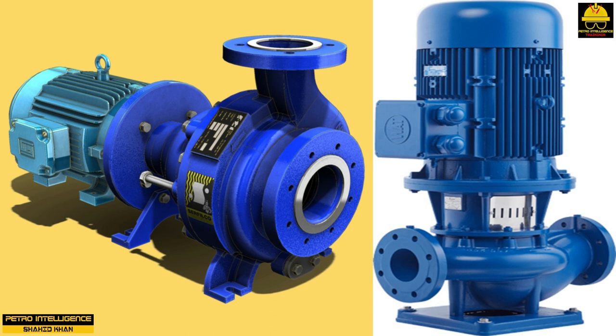Another term used in the operation of a centrifugal pump is net positive suction head required, NPSHR. Net positive suction head required is the minimum NPSH necessary to avoid cavitation. The NPSHA must be greater than or equal to the NPSHR, expressed as NPSHA >= NPSHR. It is the reduction in total head as the liquid enters the pump.